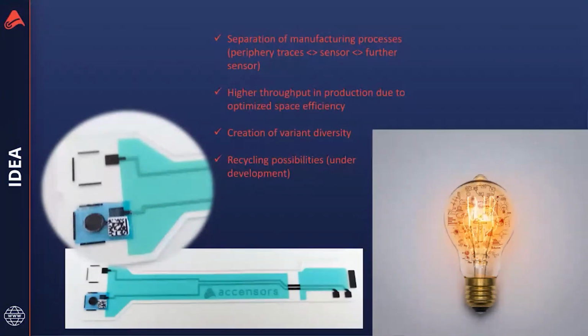And for this, we have 3 separate systems: the periphery tracks, the printed electronic board, the sensor, and of course the reference electrode. And with this, we could produce the sensor and the reference electrode in a higher throughput in the production, and that means we optimize the space. And we could bring the production costs down by a lot. And the other point is, if you separate the tracks and the sensors, you create more variant diversity.